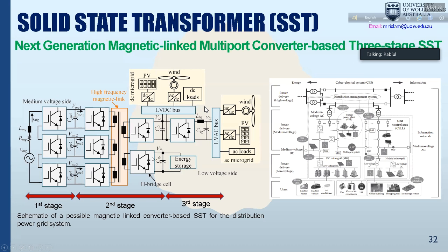It's a single unit, but it has multiple functions, and it can interconnect many things. It can interconnect different types of sources, different types of loads, energy storage. It can connect with medium voltage grid, low voltage grid, DC bus or DC grid, AC grid. And power can flow in any direction through this high frequency magnetic link.